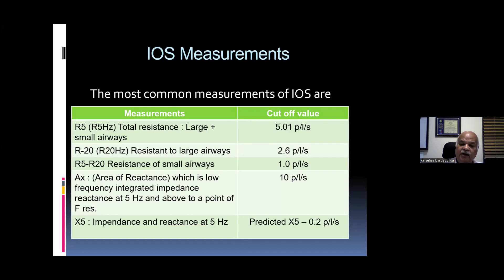So this is also very important to know, what is coherence. Coherence is the correlation between airflow and pressure. So if there is a mismatch, coherence will be below 0.6, and normal coherence at 5 Hz should always be more than 0.6, and at 10 Hz, it has to be more than 0.8. So look at the coherence in the graph that is given.